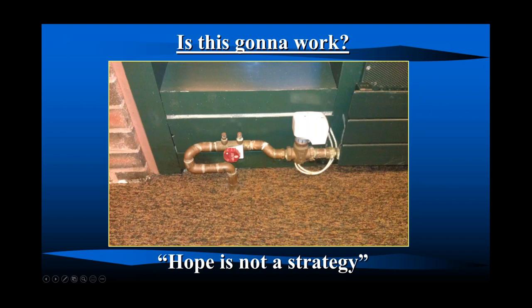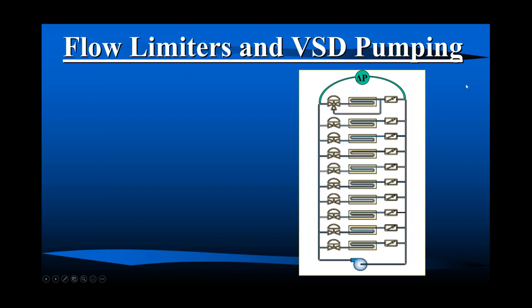So, yep. Balancing is more important than ever on these new systems, because they're going to be warm water or cool water, not hot water, not chilled water either. Good. All right. So flow limiters and variable speed pumping. So a quick basic system. Here's our pump at the bottom of the system. Here's our terminal units. And at the top, we have a three-way valve to keep water moving no matter what. And here's our pressure transducer across the index circuit of our system. There's our balancing valves and our control valves.